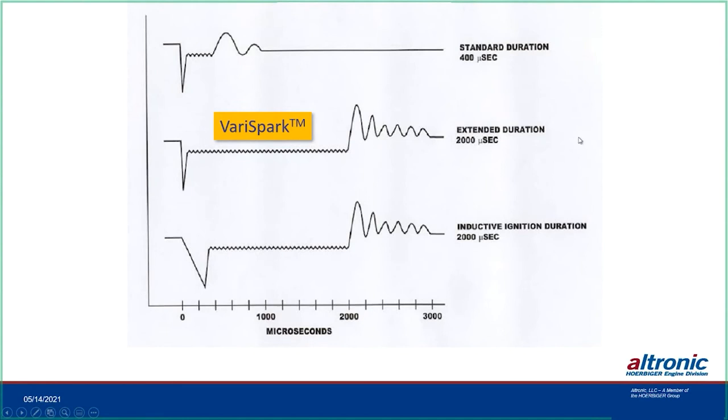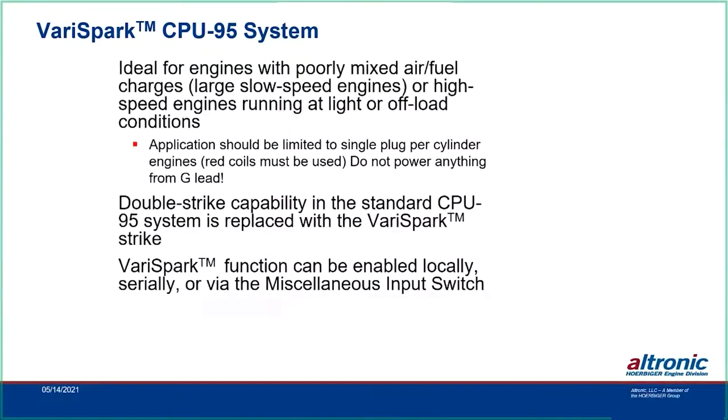VariSpark is ideal for engines with poorly mixed air-fuel ratio charges — slow-speed engines or high-speed engines running at light or off-load conditions. It is a single-plug application using the red coils, and you cannot power anything from the G-lead with that configuration. Double-strike capability is also available with the standard CPU-95 and VariSpark. The same EPROM programming used for the standard CPU-95 is used in the VariSpark and Enhanced VariSpark.